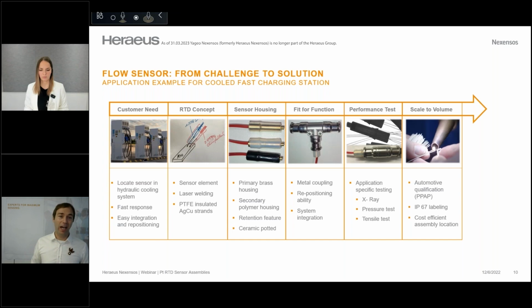And fit for function really is, okay, how can we incorporate that into the standard system of our customer? And that T has a coupling on each end that can be very flexibly positioned in the fast cooling equipment. We started with polymers of that T. You now see the metal, just to make sure that it sustains in the higher temperatures. And what you can do, you can pull out that sensor and you can put it on the other sides. You can put it on any coupling of that hydraulic cooling system in the charging station, which makes it very flexible. If you look to the left, easy integration, repositioning, this is where we said, okay, these are the features that actually allow to do that.